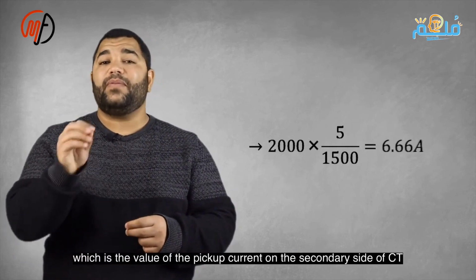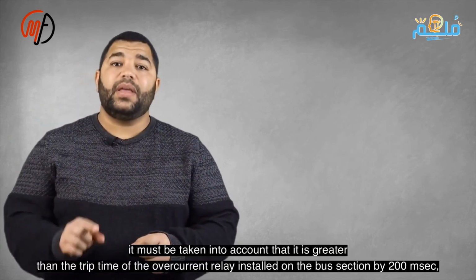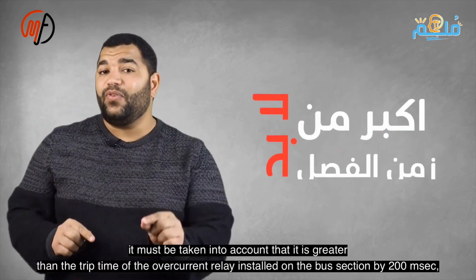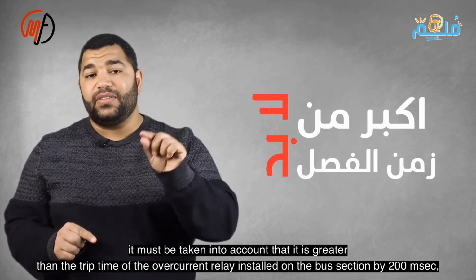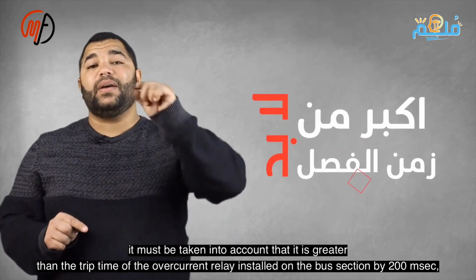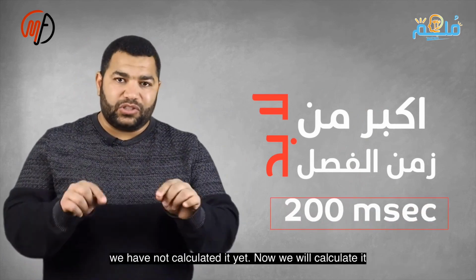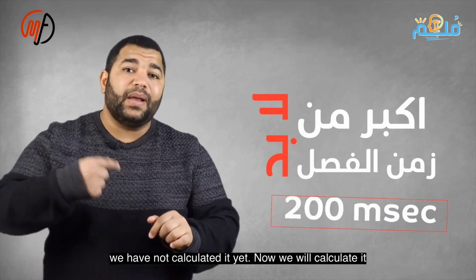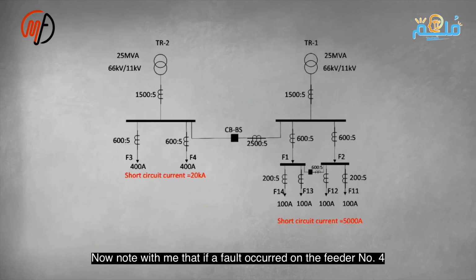If feeder 4, fed from transformer 1, fails, the bus section breaker must trip with a 200 ms margin. If F14, fed from transformer 2, fails, F14 must trip first. If it fails, then the bus section, and finally T2 must trip. Calculate bus section relay settings first. Assume max current through the bus section breaker, and feeders are supplied from the other transformer through this breaker.